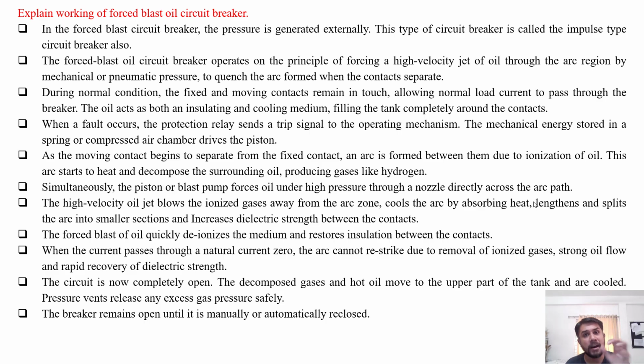Now when the current passes through a natural current zero instant, the arc cannot restrike due to the removal of the ionized particles or ionized gases, strong oil flow and rapid recovery of dielectric strength. As the rate of rise of recovery of the dielectric strength is high as compared to the restriking voltage, the arc does not restrike again. The circuit is now completely open.